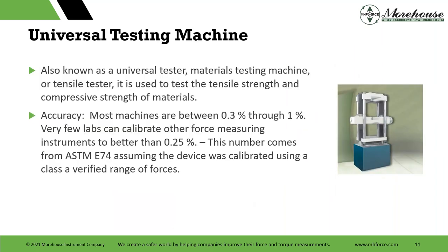So universal testing machines, this is here because many people use these as calibration standards. And if you are using them, they're used as universal test or materials testing machines or tensile testing. Often they're used to test the tensile strength and compressive strength of materials. And most machines of this nature I've seen are generally good to 0.3 through 1%, and very few labs can calibrate other force measuring instruments better than 0.25%. And that number comes from ASTM, assuming the device was calibrated using a Class A verified range of forces.